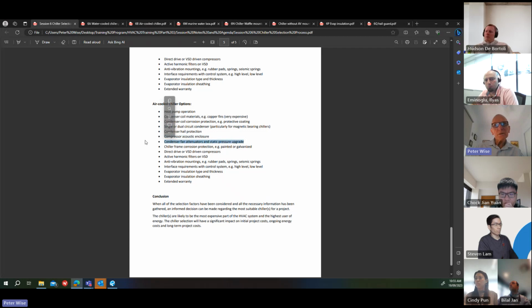Condenser fan attenuators. The attenuators won't be supplied by the chiller manufacturer. They'll come from an attenuator supplier, but the static pressure upgrade, you'll need to request that from the chiller supplier. So you might need to go to an axial fan instead of a propeller fan to get the extra static. That's quite common because they do make a bit of noise. You can get corrosion protection on the frame. So corrosion protection painting, for instance, or get the frame, well, the frame will be galvanised anyway, no doubt. So you can get extra coatings on top of that.